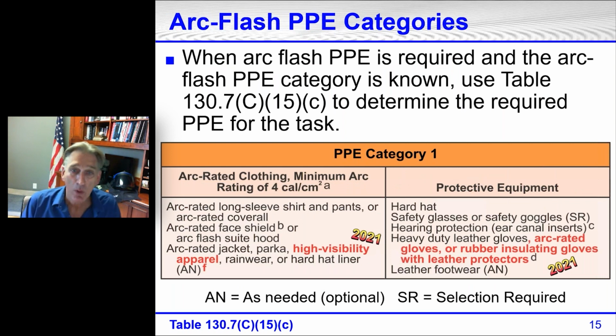When arc flash PPE is required and the arc flash PPE category is known, use Table 130.7(C)(15)(c) to determine the required PPE for the task. All right, this is category 1. It gives us information: you have to wear arc-rated long sleeve shirt and pants, or arc-rated coverall, and an arc-rated face shield, with a footnote, or an arc-rated arc flash suit hood. This is category 1. The minimum arc rating for category 1 is 4 calories per square centimeter.